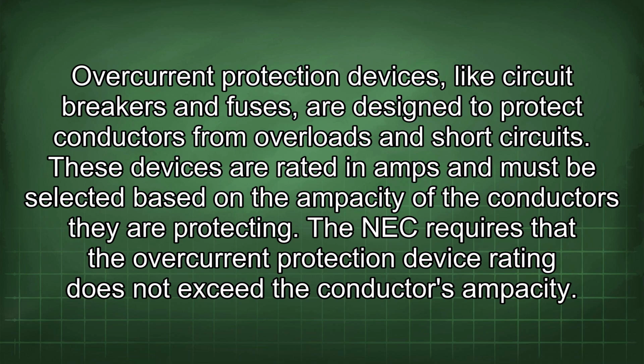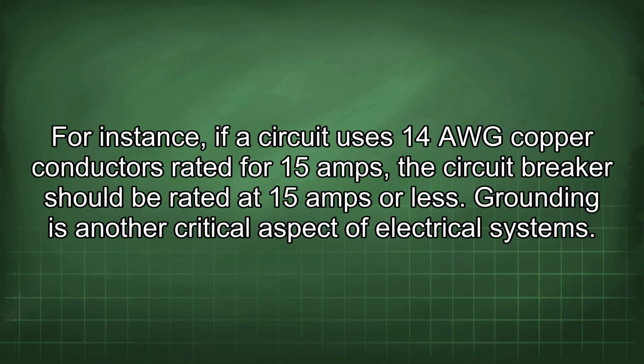Overcurrent protection devices, like circuit breakers and fuses, are designed to protect conductors from overloads and short circuits. These devices are rated in amps and must be selected based on the ampacity of the conductors they are protecting. The NEC requires that the overcurrent protection device rating does not exceed the conductor's ampacity. For instance, if a circuit uses 14 AWG copper conductors rated for 15 amps, the circuit breaker should be rated at 15 amps or less.